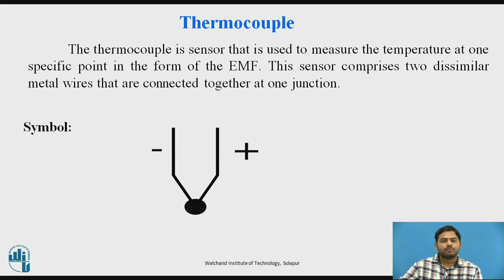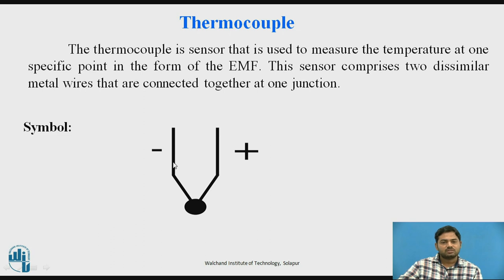Now, coming to the thermocouple — another type of temperature transducer. A thermocouple is a sensor used to measure temperature at a specific point, and it provides an electromotive force (voltage) at the output which is proportional to the temperature. Basically, a thermocouple has two different types of conductors joined at one point, called a junction or hot junction. These two wires are of different materials — for example, copper and iron.